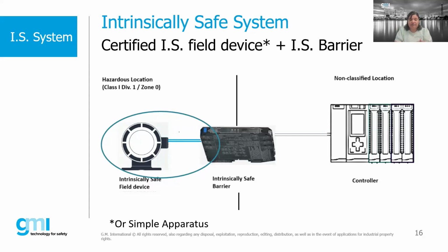I put an asterisk in there because it's an intrinsically safe field device or an associated apparatus, or a simple apparatus. A simple apparatus is a device that is so simple that it doesn't really need to be certified for intrinsic safety applications, but it cannot store or generate more than 1.5 volts, 100 milliamps, and I think 25 milliwatts. An example would be a thermocouple, an RTD, a push button, just a short circuit device like a push button. So something very, very simple could be considered a simple apparatus. And as long as it's connected to an associated apparatus, you are creating this intrinsically safe loop. And all that is in the standards that we just talked about.